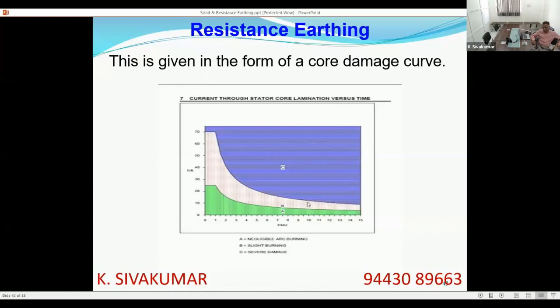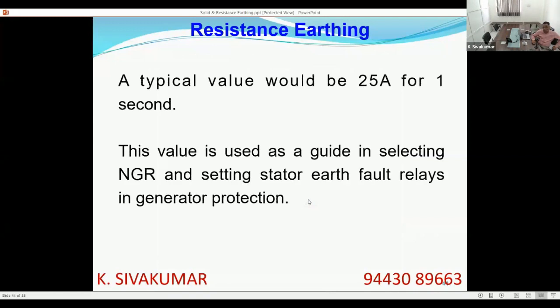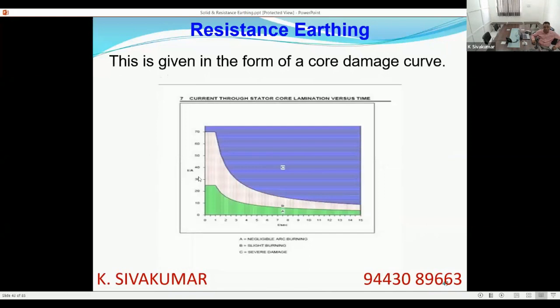You can get this data from the generator manufacturer or the motor manufacturer. You can demand, please give me the core damage curve of your machine. They will give it. So if you see, typically 25 ampere for 1 second is tolerated. If you see, this is the 25 ampere and 1 second.